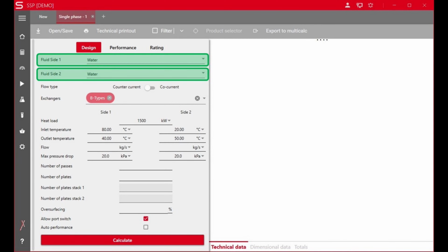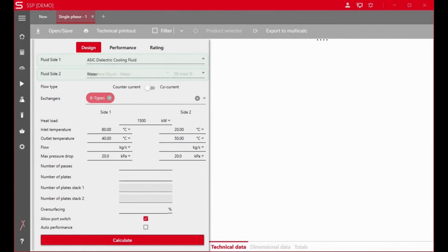SWEP recommends having fluid 1 be the hot fluid, so we'll change this to our custom ASIC dielectric cooling fluid created earlier, and fluid 2 will be the 50-50 glycol water mix. Make sure the flow type is set to counter current and the exchanger selector is set to B types.